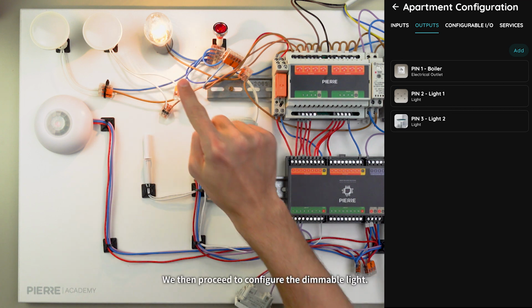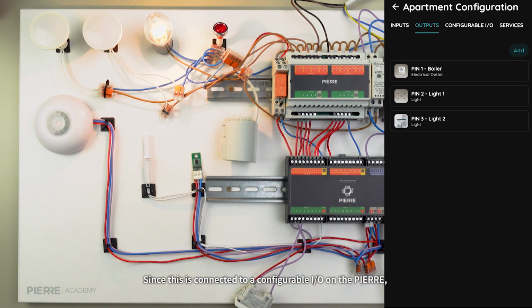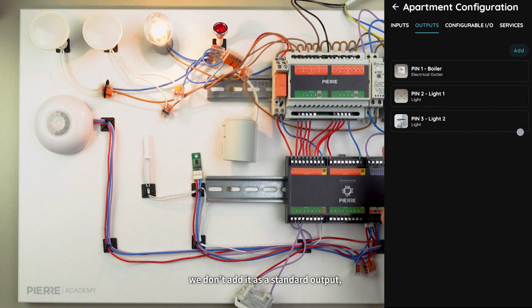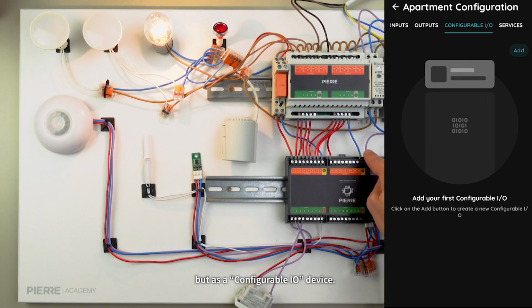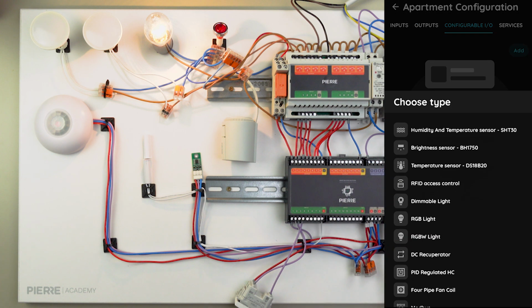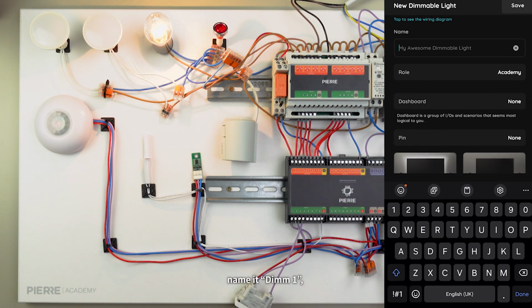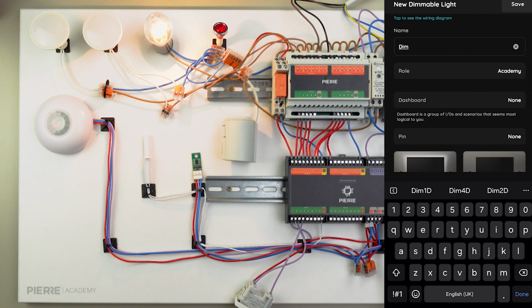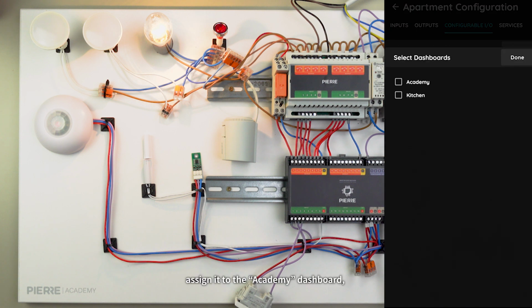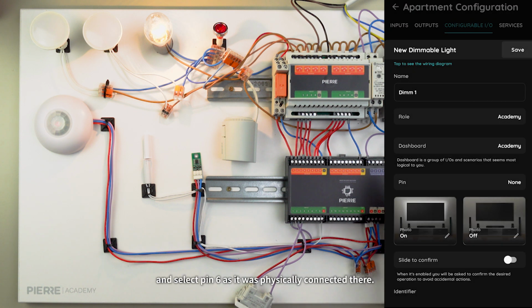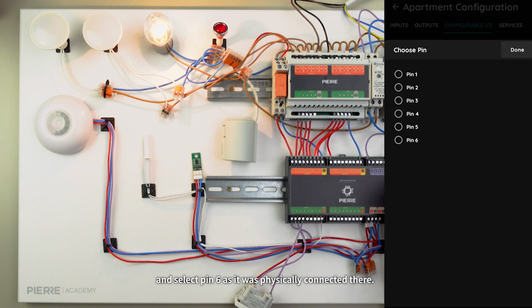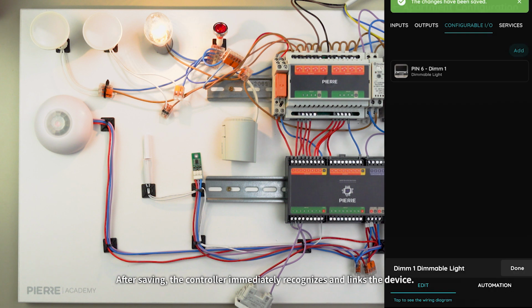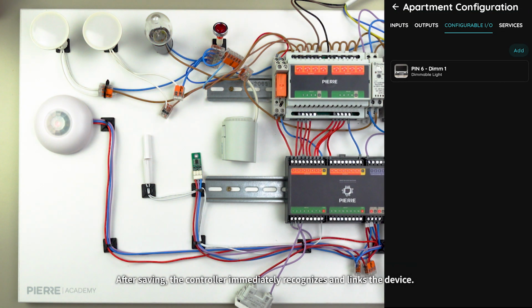We then proceed to configure the dimmable light. Since this is connected to a configurable I/O on the Pierre, we don't add it as a standard output, but as a configurable I/O device. We tap Add, select Dimmable Light, name it Dim1, assign it to the Academy dashboard and select pin 6 as it was physically connected there. After saving, the controller immediately recognizes and links the device.